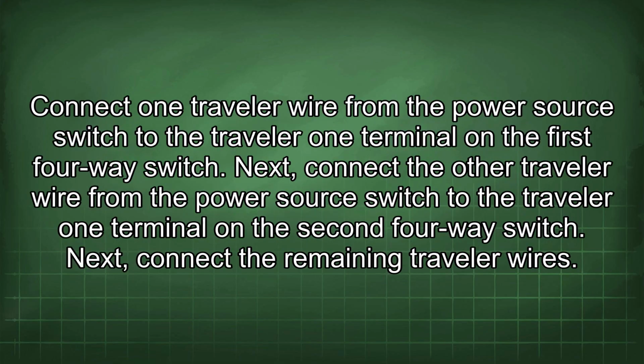Connect one traveler wire from the power source switch to the traveler 1 terminal on the first four-way switch. Next, connect the other traveler wire from the power source switch to the traveler 1 terminal on the second four-way switch. Next, connect the remaining traveler wires.